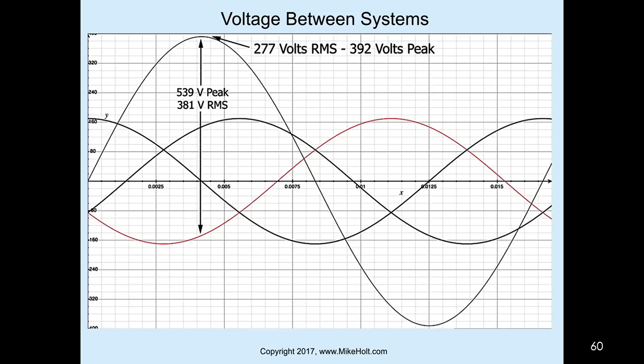All right. Now this, without getting into details, Eric. This is the 120 volt phase that we're going to be looking at, and this is the 277, which would have given you the maximum between the 277, and we'll mark this down as 120. And the difference between this instant point and this instant point, we'll make sure we touch those two instant points, is 539 peak volts, and the RMS voltage is about 70.7% of that voltage, which gives us 381 volts.